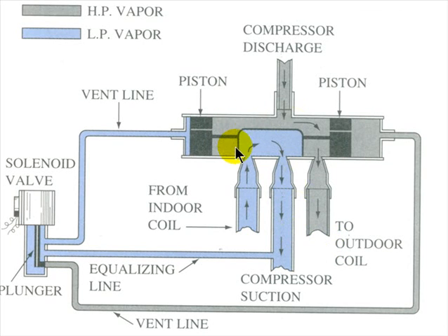Here's the slide. I think we're in the heating position here. It doesn't matter. What I want you to be familiar with is the way this works. Now, attached, and we've separated it here so you can see it, in fact, I didn't separate this, the good people from Trane who gave me this slide did. Now, we have capillary tubes. This piece is actually mounted right on the valve, but it's difficult to see it that way. So they took it off the valve and spread it out so it makes more sense.